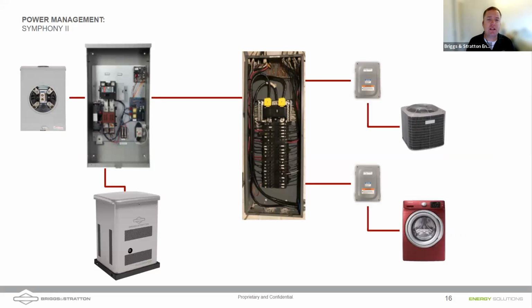One thing that's really unique, and let's just imagine we don't have batteries, but we want to add a generator, and we also have solar on the home. One concern is if grid goes down, the generator starts, and you have solar landed in the main electrical panel. Well, because of its anti-islanding requirements, the solar is going to disconnect if it sees utility goes away. But here you are using a generator to create a grid in your home. The solar may come back on, latch on to the sine wave generated by the generator, and then start to try backfeeding into the home.